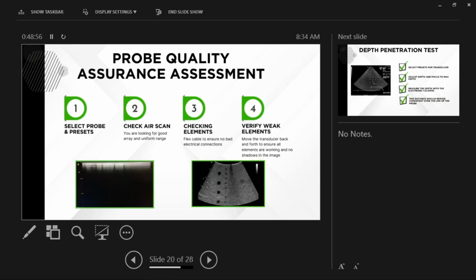The other thing I would do is flex here at the strain, right? Make sure I don't have any dropout or any issues. If there's a spot in the cable that looks like it's been run over, you could either see it with markings or a little nick. I would go to that part of the cable, give it a couple of flexes there, and make sure I don't see any 2D speckles or anything of that nature. Again, I would flex the strain at the probe connector, and then sometimes give the probe connector a little wiggle.